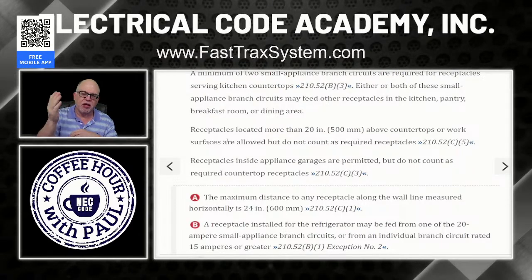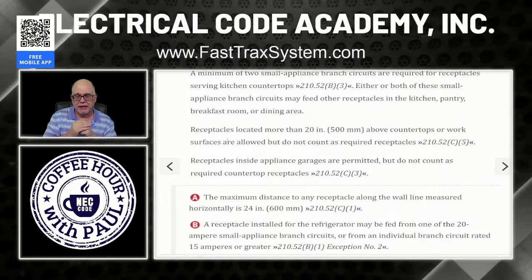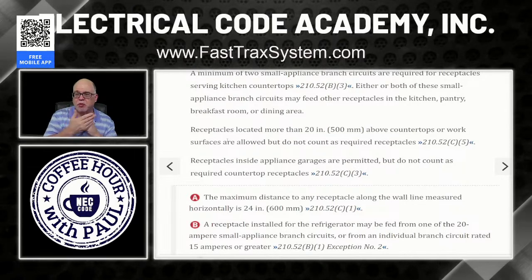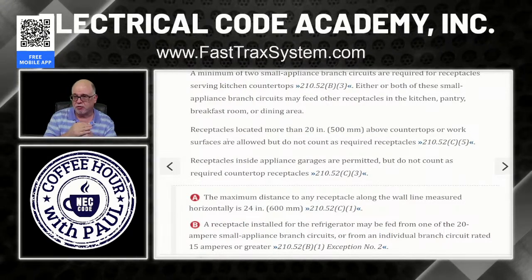Well, the same thing goes for this when you're doing countertop receptacles. If the receptacle's above 20 inches, it doesn't mean it can't be there, but it can't count as the small appliance branch circuits, okay? Also, those receptacles that you put up high really should not be on the small appliance branch circuit if it's for something like the microwave or something else. So be very careful in your placement.